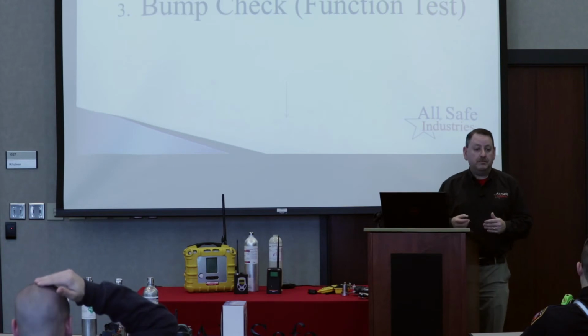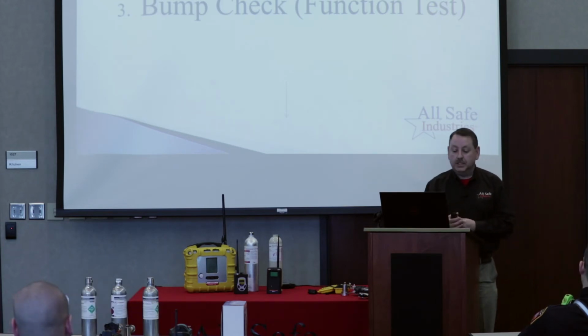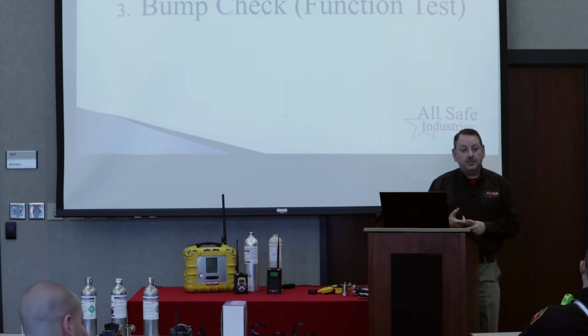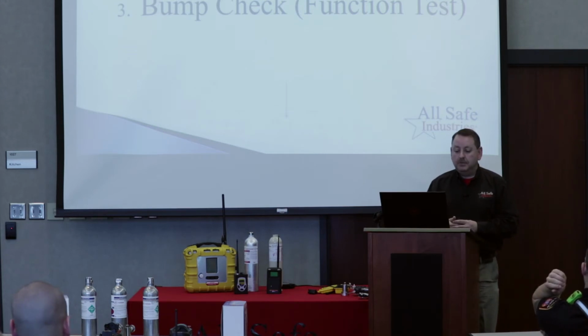They're very important. I've developed this over 22 years of doing this. The first step is always to do a fresh air calibration. You don't have to do the fresh air. You could skip it, but I like to start with a fresh air calibration because you never know if the person before you maybe shut the meter off while it still had some gas inside. Of course, the pump's running, but I just like to start with a fresh air calibration if you can. Make sure you're in fresh air if you're going to do that.